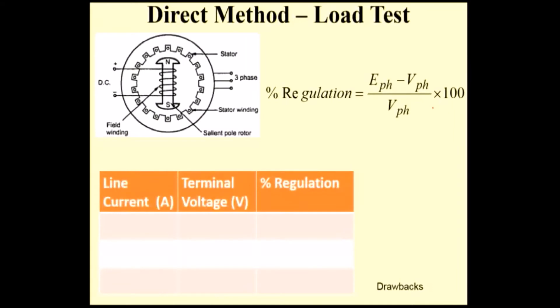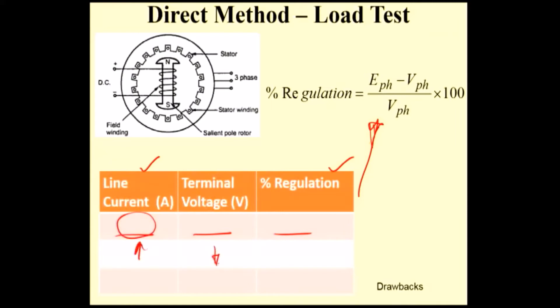This is the tabular column for the direct load method. First you have to set the no-load arrangement; load should be in no-load condition. Then you have to take the terminal voltage, then the line current. Normally during no load, the line current will be very less to meet the losses. Then you can calculate the regulation using this formula. Then gradually increase the load — the current increases and the terminal voltage normally decreases. Like that, gradually increase the load up to rated current, take the terminal voltage, and calculate the percentage regulation.